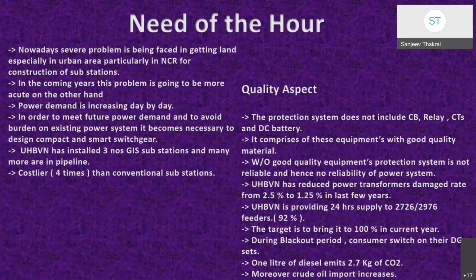Quality aspect. The protection system does not include only circuit breaker, relays, CTs and DC battery, but it comprises these components with good quality material. Without good quality material, the equipment's protection system is not reliable and hence there is no reliability of the power system. I am pleased to share that UHBVN is very keen to install good quality equipment and is working sincerely in this field, as a result of which we are able to reduce the power transformer damage rate from 2.5% to 1.25% in the last 5 years and are trying to bring it to less than 0.5%.